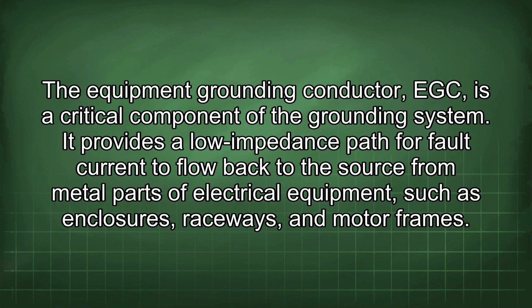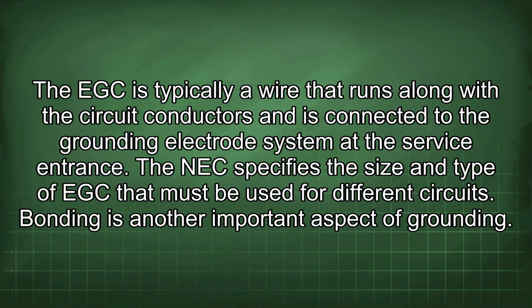The equipment grounding conductor (EGC) is a critical component of the grounding system. It provides a low impedance path for fault current to flow back to the source from metal parts of electrical equipment, such as enclosures, raceways, and motor frames. The EGC is typically a wire that runs along with the circuit conductors and is connected to the grounding electrode system at the service entrance. The NEC specifies the size and type of EGC that must be used for different circuits.